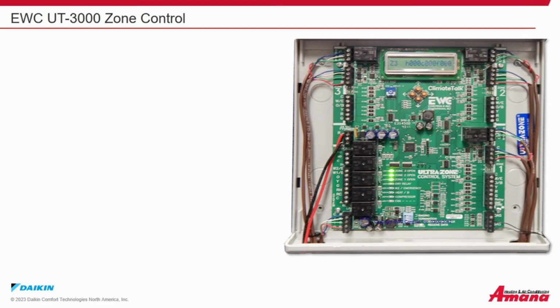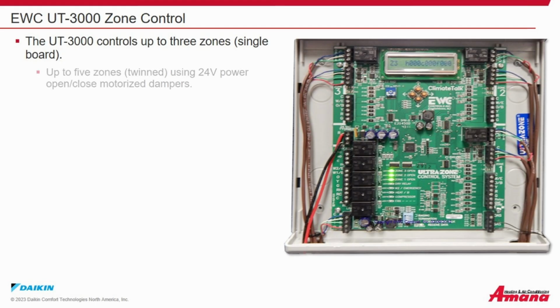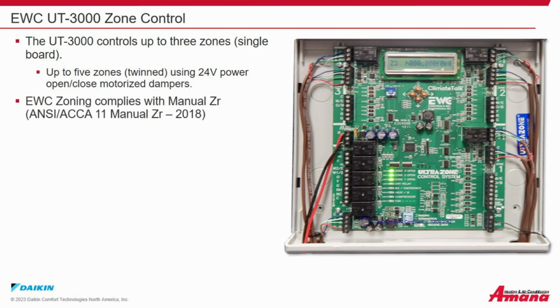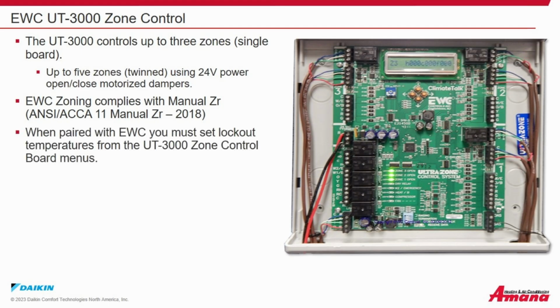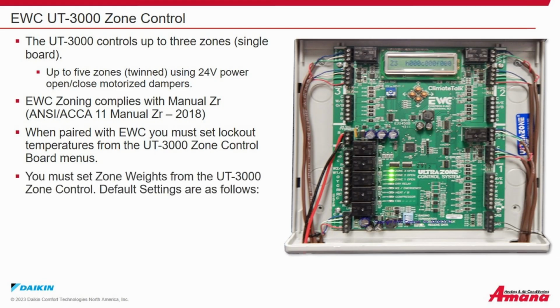EWC UT3000 Zone Control. The UT3000 controls up to 3 zones using a single board. Up to 5 zones twinned using 24-volt power open and closed motorized dampers. The EWC zoning complies with Manual ZR, which is the ANSI or ACCA 11 Manual ZR-2018. When paired with the EWC, you must set lockout temperatures from the UT3000 zone control board menus. You must set zone weights from the UT3000 zone control.